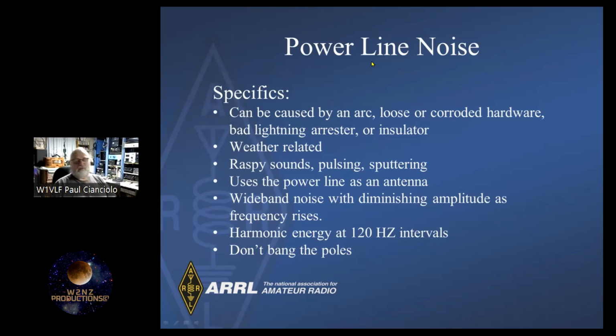Specifics - okay, let's look at power line noise. I hear a lot of people say, well, there's a transformer right outside my house. Transformers typically don't make noise, but things that do make noise are arcing, loose or corroded hardware. Even if a piece of hardware is out in the field - you know why they call them transmission lines? Because they're transmission lines - and you put a piece of metal that's loose on a nut or bolt up on one of the towers in the field between those transmission lines, it's going to arc, and that's the noise you're hearing.